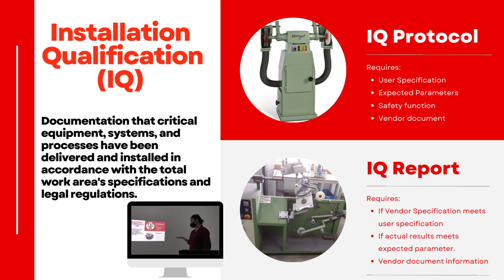And then after all the information is gathered, we will need to get approval from the operation head department, which is Ms. Pique Cho. And then we will have to go and validate if the machine meets the specification requirement. After that we will do the IQ report. For the IQ report, we need to ensure that the vendor specification meets the user specification, and whether the actual result meets the expected parameters and also the vendor document information.